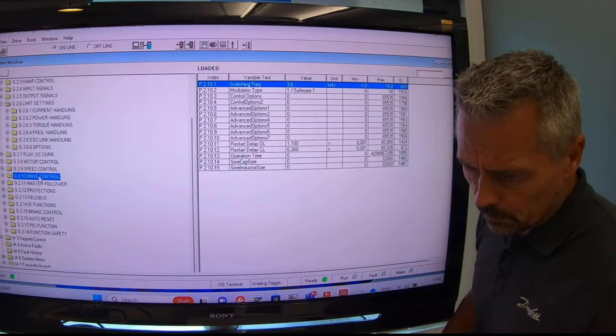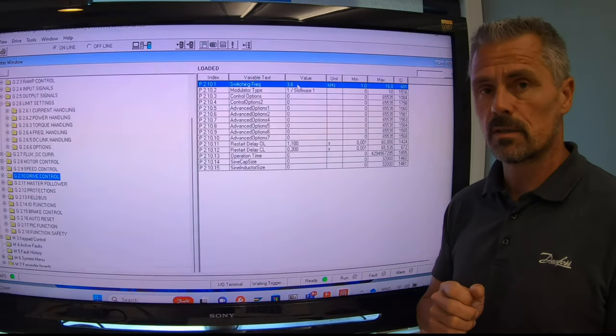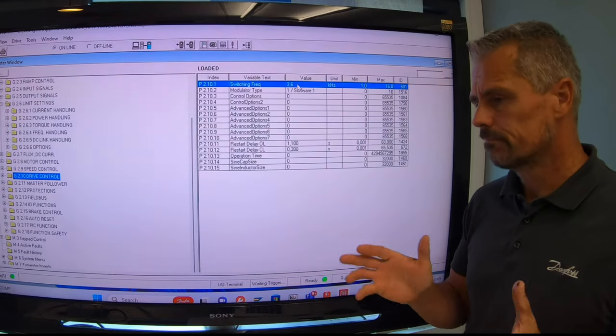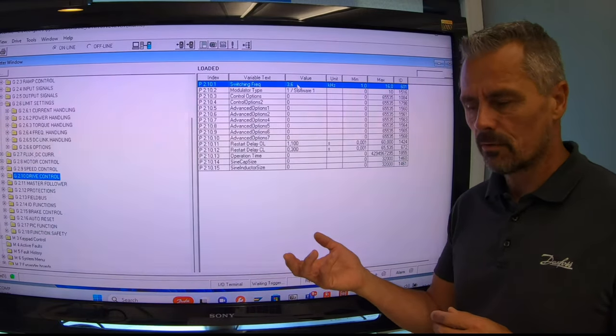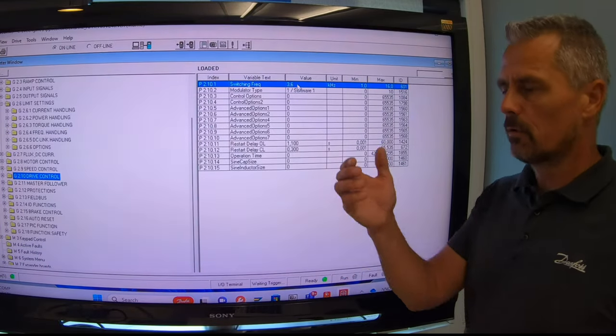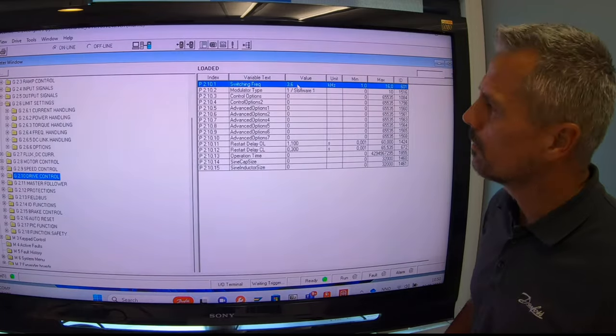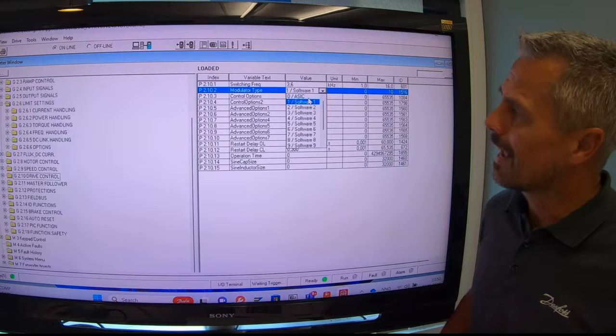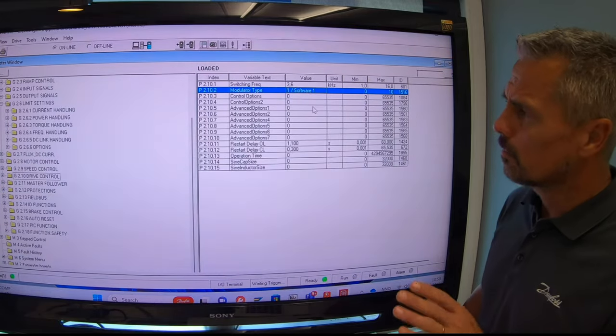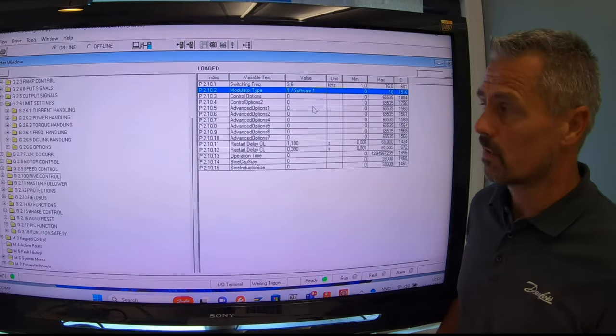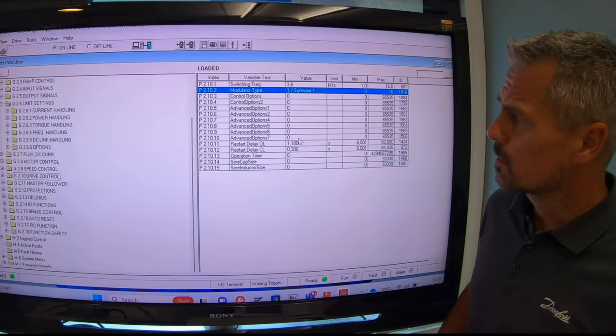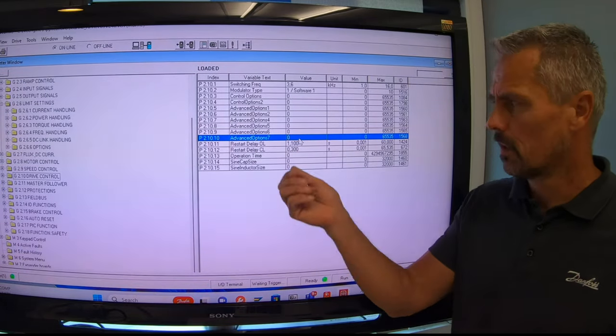In the drive control, I have selected 3.6 kilohertz, actually that is the default switching frequency. In the marine application, 3.6 is something between - not too high which gives IGBT over temp if you push it too hard, and not too small because that will give a pulse width resolution which is too small for a permanent magnet motor. So 3.6 is a quite common number for most permanent magnet motors. Software 1 - do not select ASIC. Don't do software 2 either. Software 1 is the one. And don't change these parameters later because then you have to do the identification runs one more time. In advanced options, there is nothing right now, but we will change that after a little while, especially if you have wrong direction on the motor.